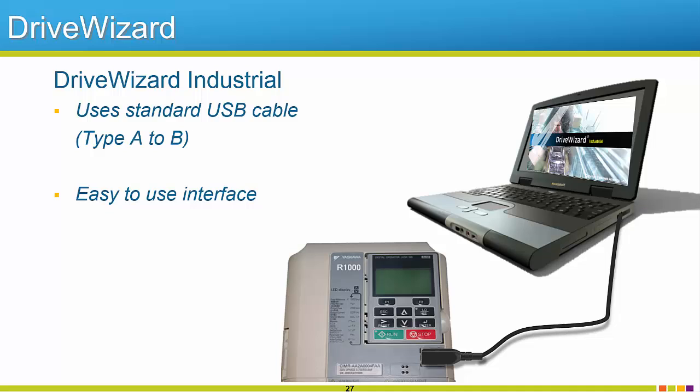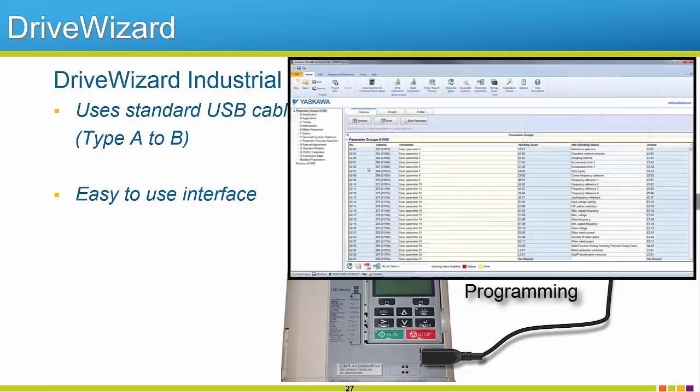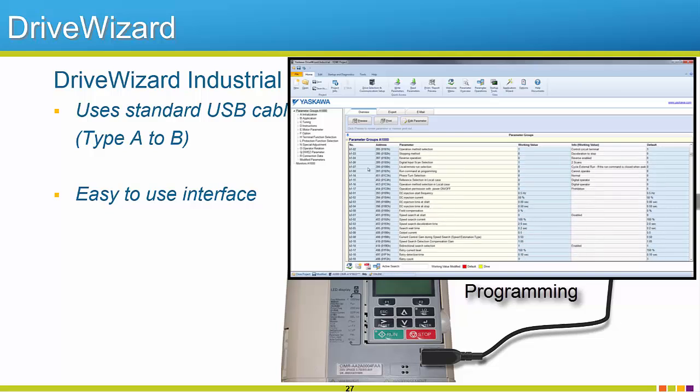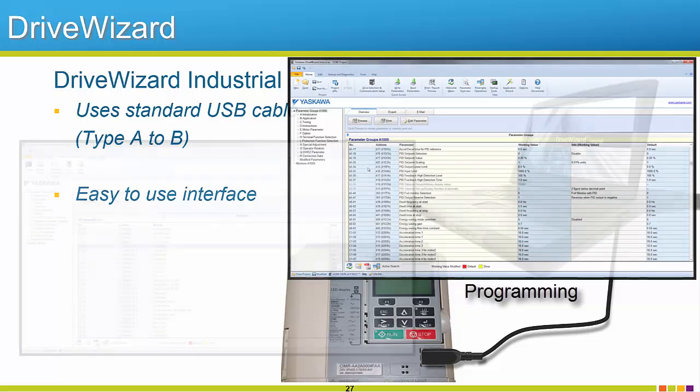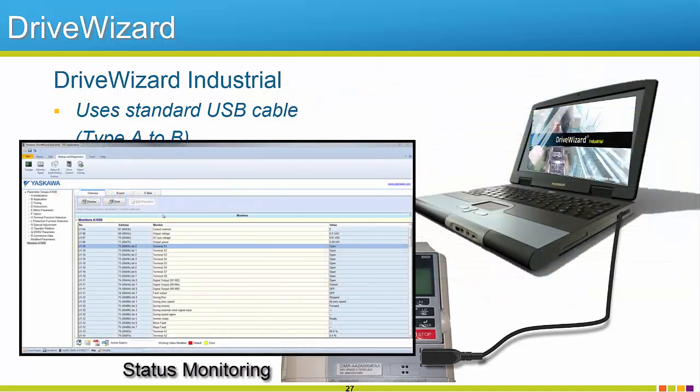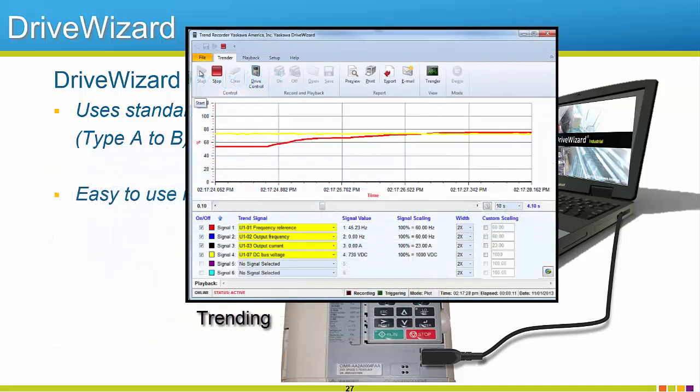To accelerate setup and programming further, Yaskawa's PC tool, DriveWizard Industrial, can connect to the R1000 with a standard type A to B USB cable. This software is free. The software features the ability to create and save parameter files without the need of being physically connected to the unit itself. Programming from the R1000 can be backed up for storage as a number of different file types for personal reference or for sharing and sending to others. Live parameter editing can be performed as well as graphic trending for up to six monitors at a time.